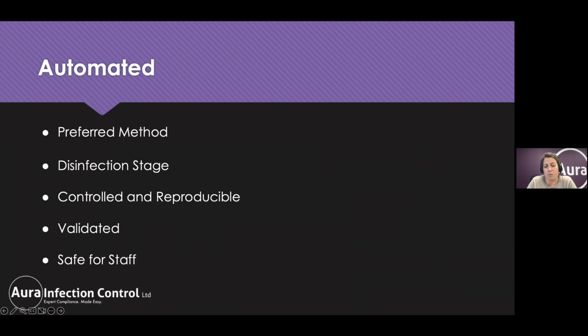The washer disinfectors will go through the same 5 stages. They subject instruments to a flush first of all, to remove any water-soluble proteins and gross contamination. It will then wash instruments, dosing a set amount of detergent, or detergent and disinfectant, depending on what you use. It will then rinse items before thermally disinfecting them. Thermal disinfection is achieved by subjecting these items to a 90 degree temperature for a 1 minute holding time.